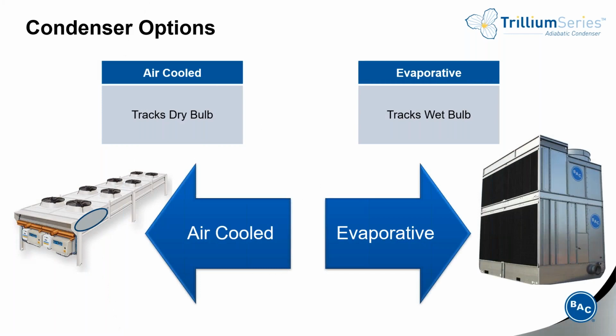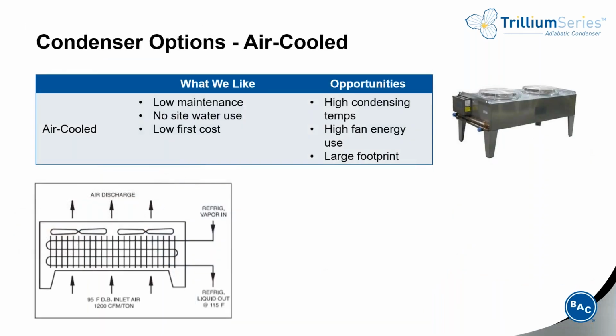So traditionally, we've had two choices when it comes to choosing condenser equipment. Air-cooled equipment that tracks dry bulb temperatures, which typically means larger compressors and more energy use year-round, or evaporative condenser products, which tracks wet bulb temperatures, which allows for lower condensing temperatures, smaller compressors, lower energy use, but does come with the need for additional maintenance in terms of water treatment. So let's look a little bit more specifically at the air-cooled option.